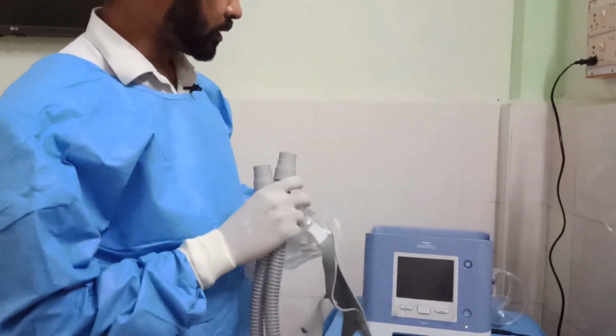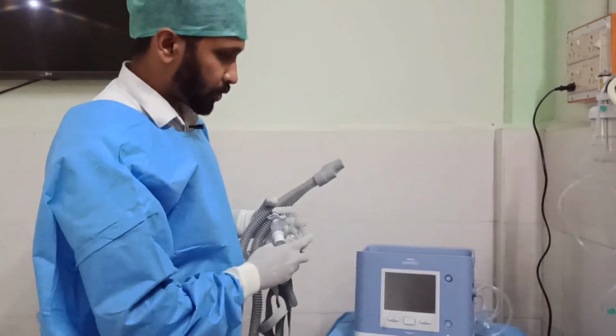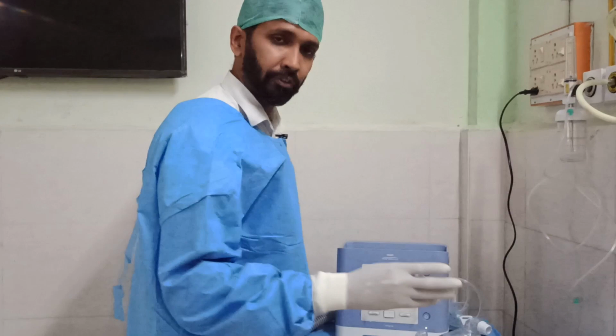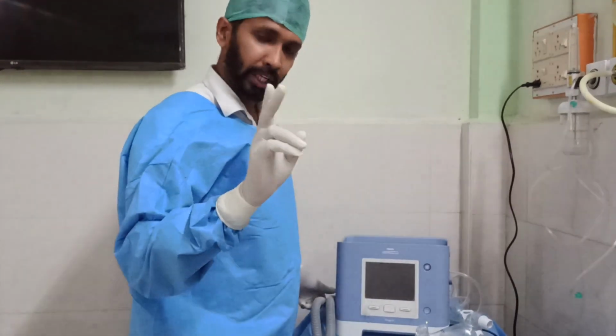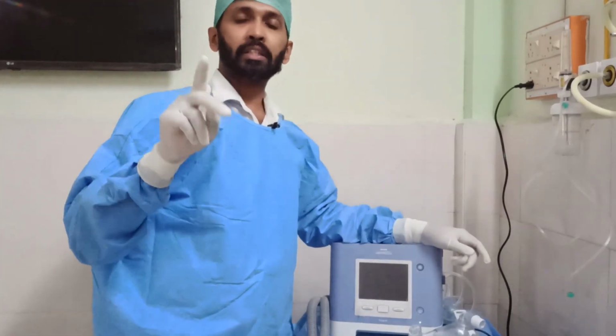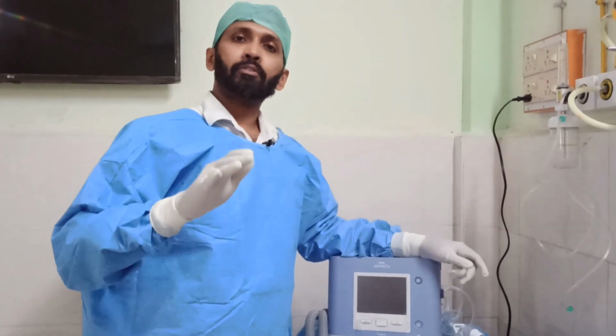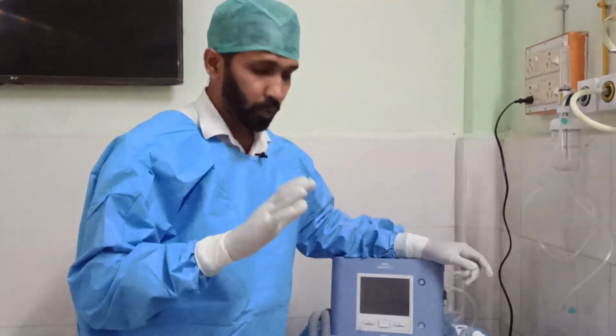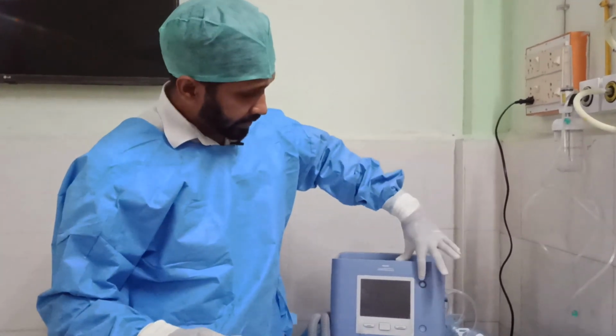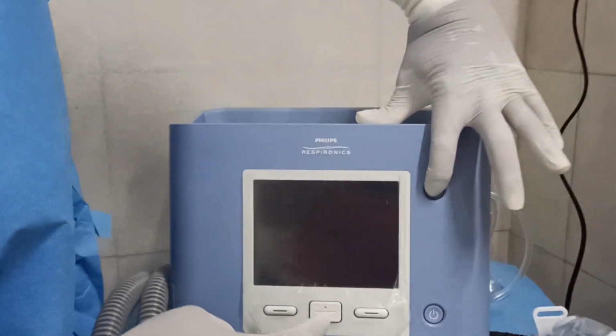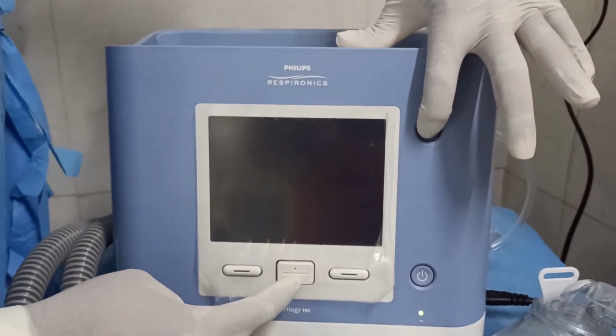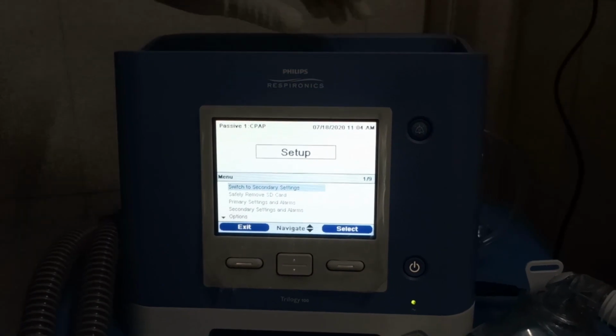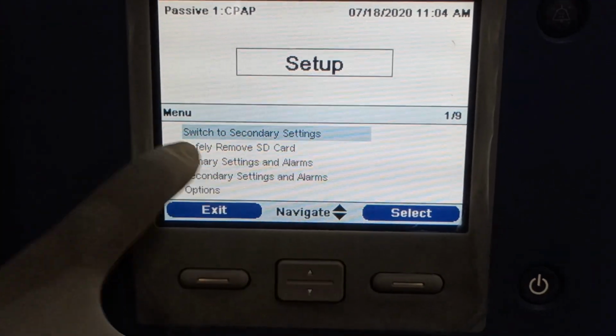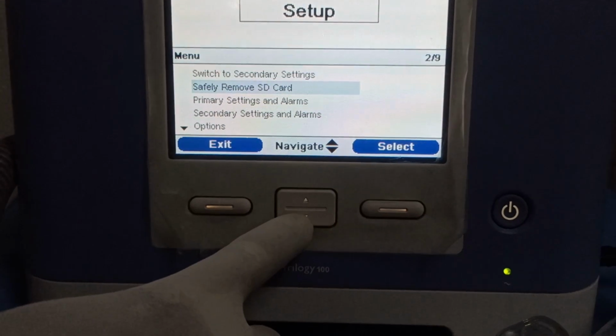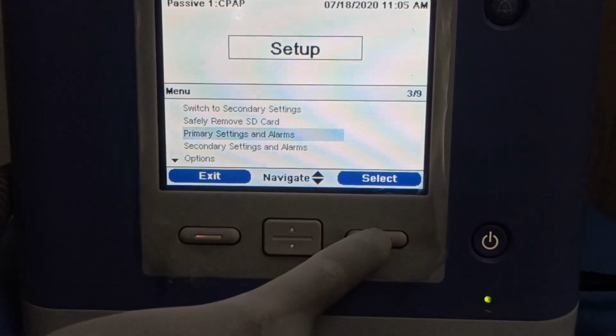Before turning on this machine, to show you the two circuit types, invasive and non-invasive: one is the active type and another is the passive type. Active type is for invasive ventilation and passive type is for non-invasive CPAP ventilation. So how to change the circuit type? First, press the alarm button along with the down button. If you press for some time, you can see a setup screen come up. Go to primary settings and alarms, and select.